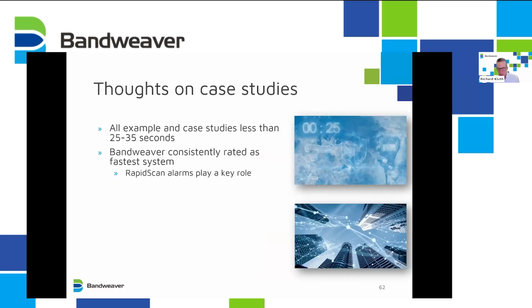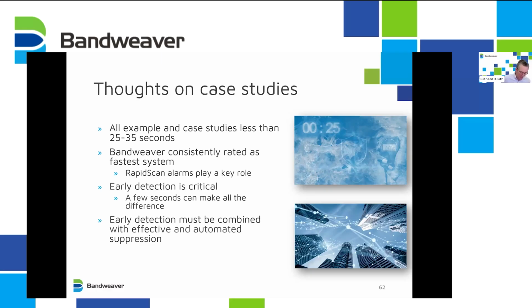So just to summarize the case studies, you can see all of them are 25 to 35 seconds. We were consistently rated as the fastest system, and the RapidScan alarms play a key role in that. Early detection is critical. A few seconds can make all the difference. But detecting's not enough. You've got to do something about it. So increasingly, we're saying this needs to be with automated suppression, so that you're taking action within that time frame. So the whole system has to be automated. And you have to have complete confidence in the system to have an automated system.